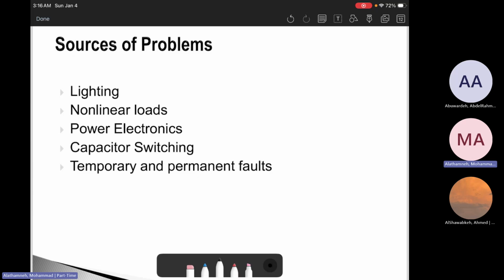The other thing, nonlinear loads. Nonlinear loads draw currents in non-sinusoidal shape. Those are creating harmonics. As an example, LED drives, chargers, variable frequency drivers, rectifiers. We can try to solve them by installing some harmonics filters. As an example, shunt active power filters are being used to solve such nonlinear loads phenomenon.